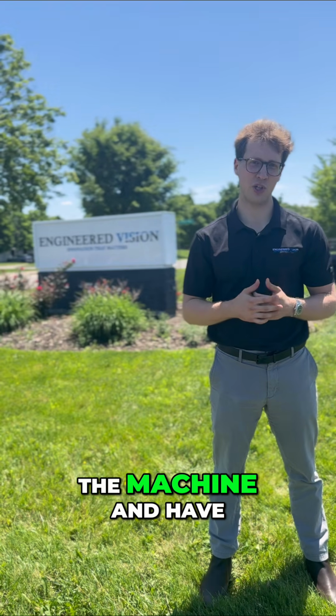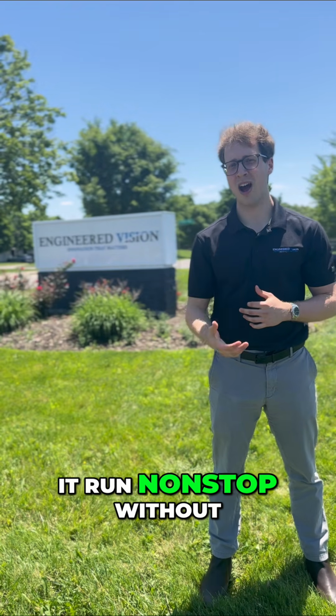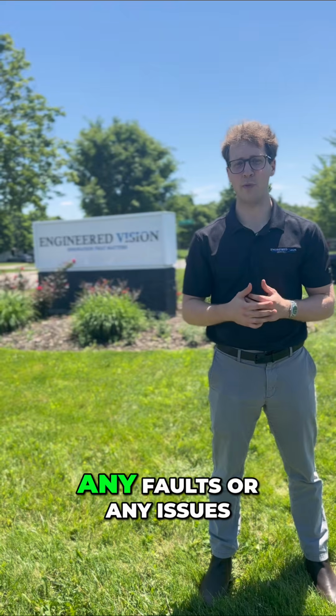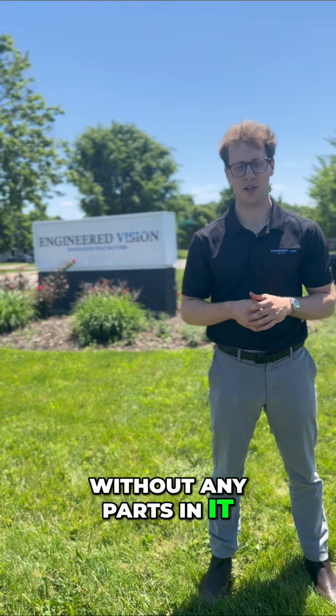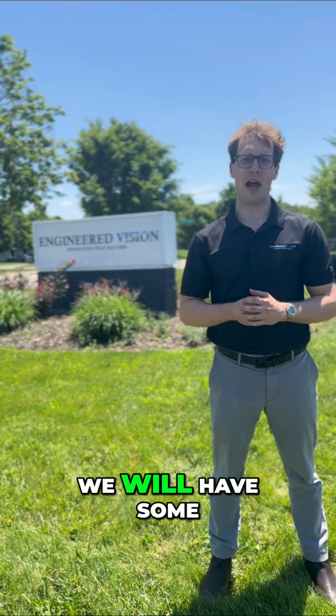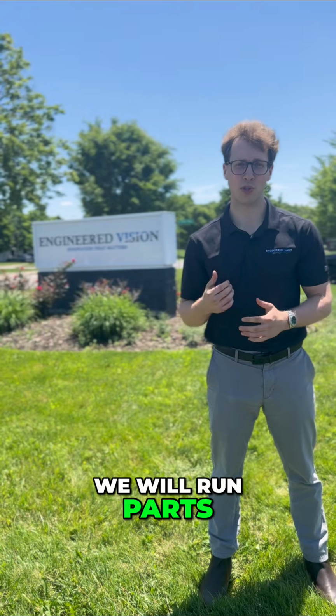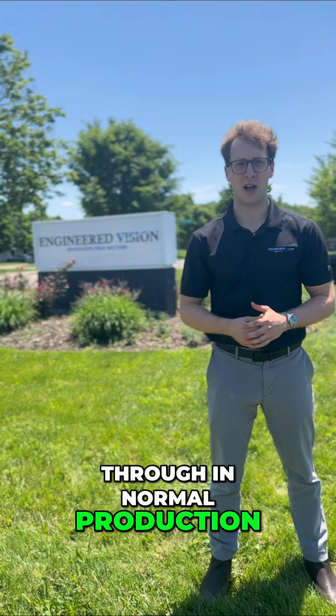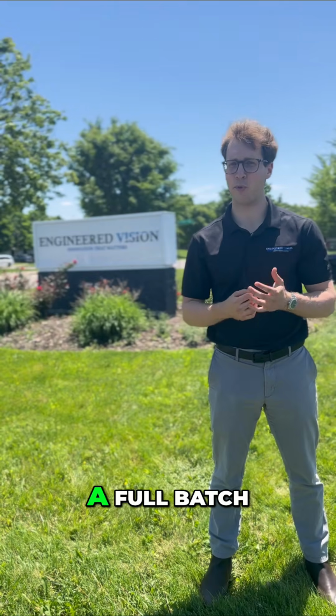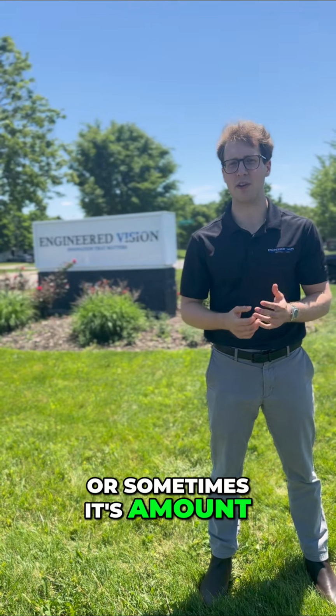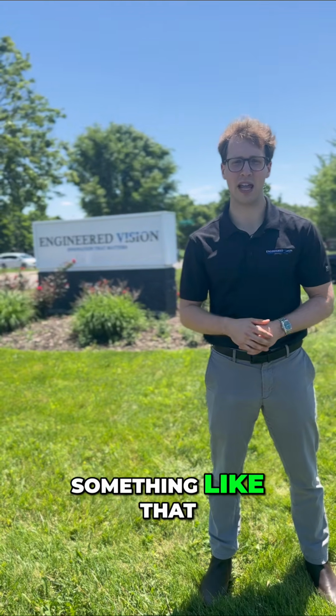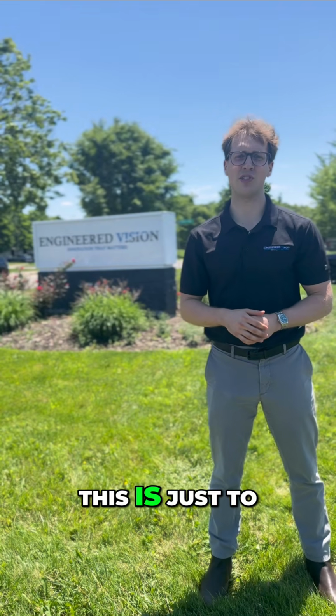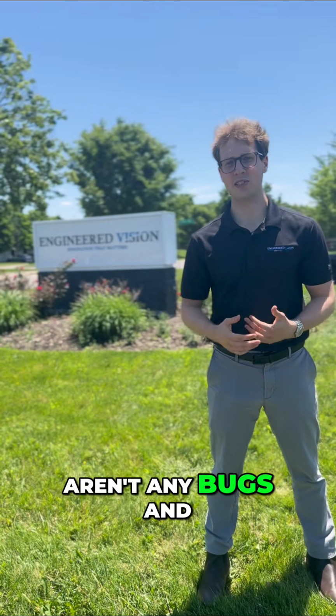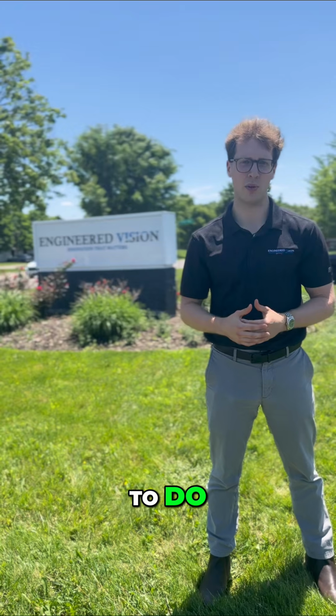So we will start the machine and have it run non-stop without any faults or any issues, without any parts in it. And then after that, we will have some amount of time where we'll run parts through in normal production. Typically that's either an amount of parts that we want to get through, a full batch, or sometimes an amount of time as well, a couple of hours, something like that. And really, again, this is just to make sure that there aren't any bugs and that it's doing everything that we want it to do.